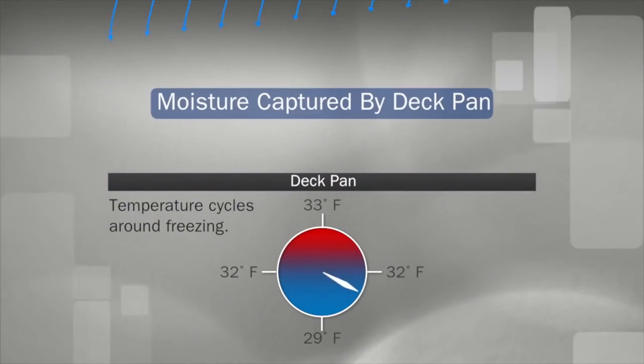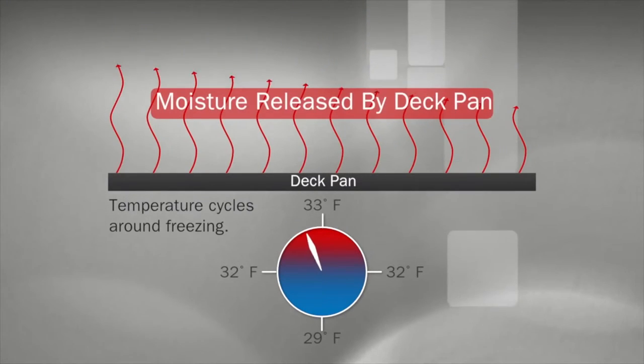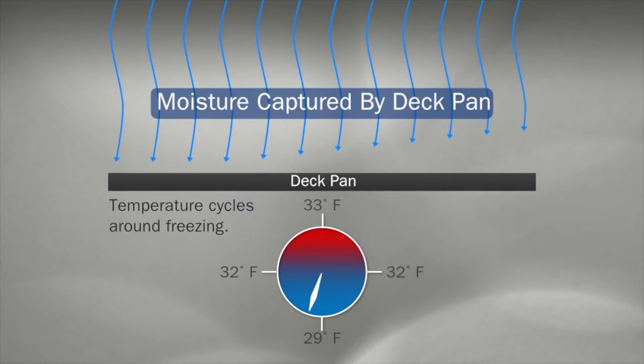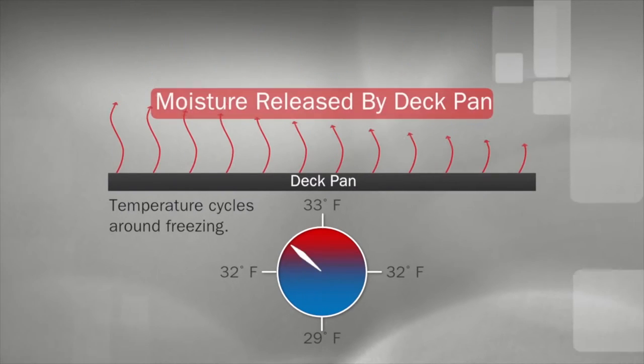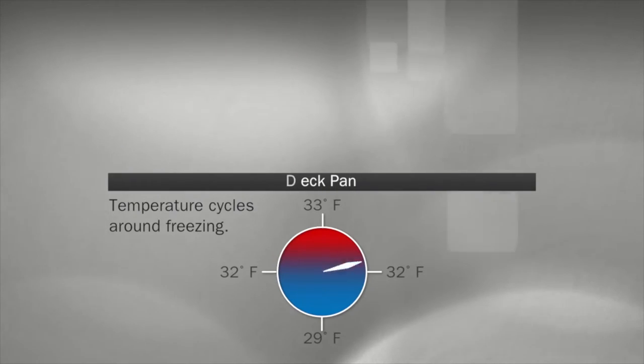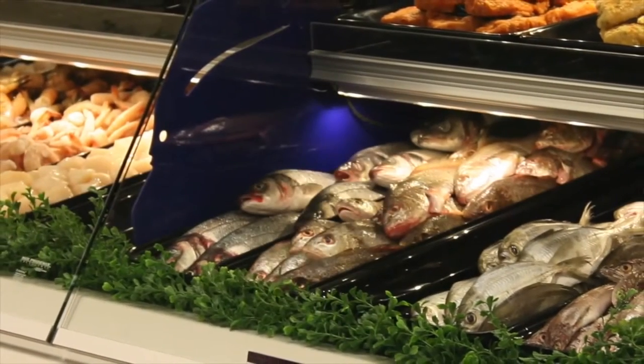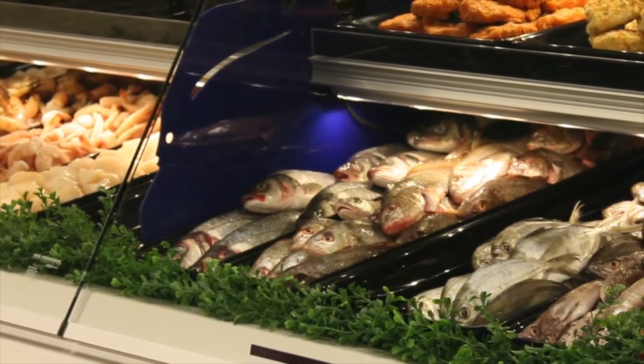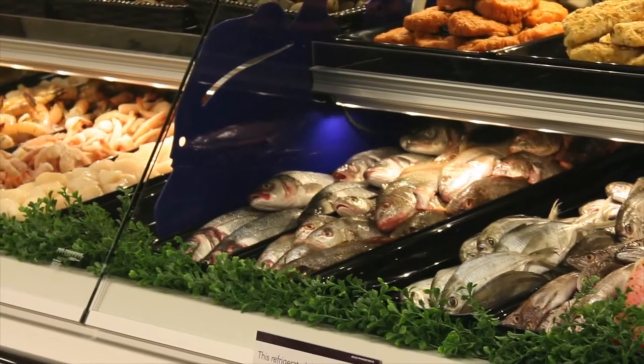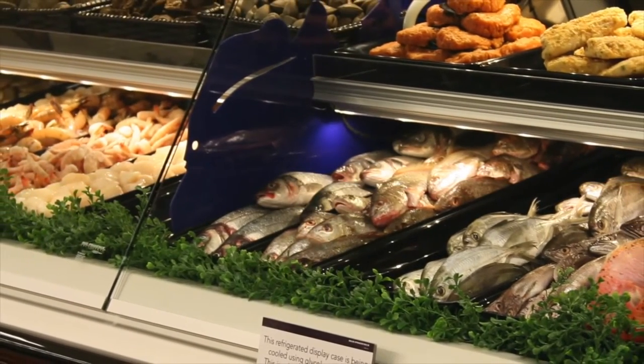The key to this high humidity environment is the fact that by design the Coolgenics case does not reach a steady state operating temperature. Coolgenics pulse flow control allows for the Coolgenics pans and gravity coil to freeze and thaw to create a high humidity environment surrounding the Coolgenics pans and any product merchandised on them. This helps maintain product moisture content and reduce product shrinkage.